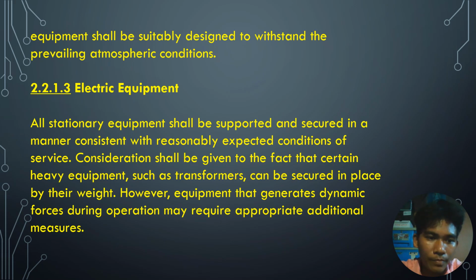Electric equipment. All stationary equipment shall be supported and secured in a manner consistent with reasonably expected conditions of service. Consideration shall be given to the fact that certain heavy equipment, such as transformers, can be considered secured in place by their weight. However, equipment that generates dynamic force during operation may require appropriate additional measures.